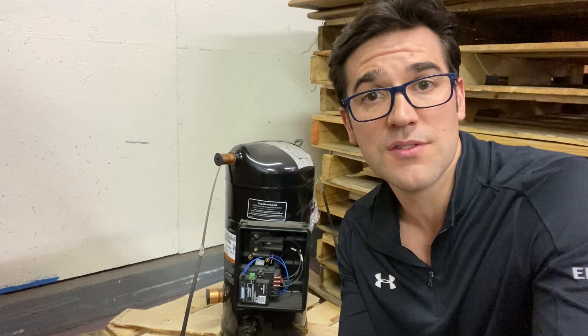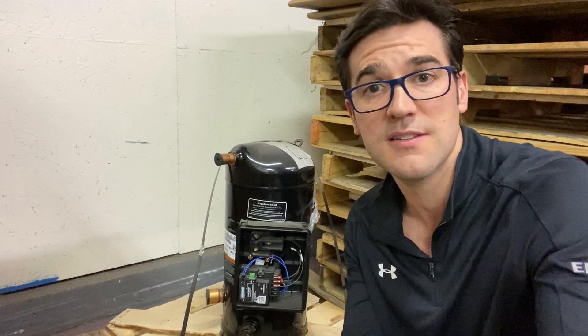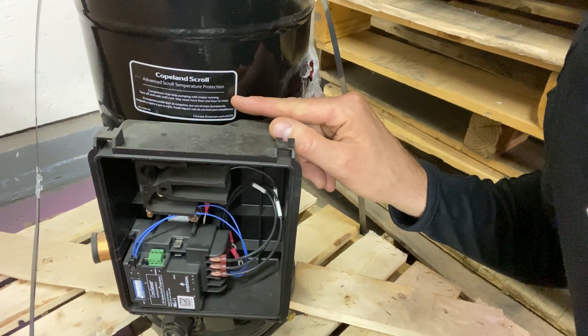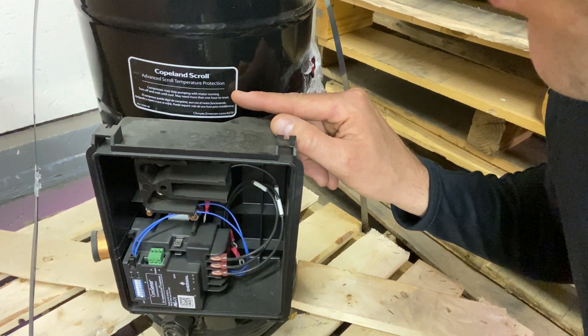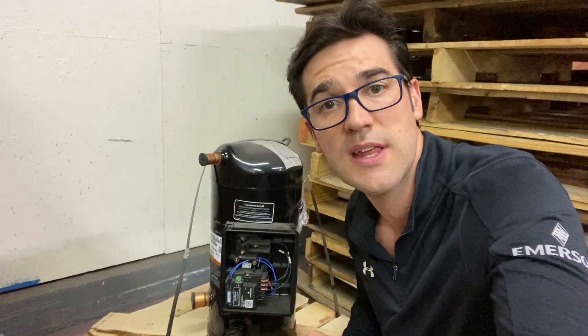It's very important to understand the different compressors you're working on, because this device is not in all scrolls — it's in some ZPs, some ZRs, some ZBs, lots of different models. The label right here says: 'Copeland Scroll Advanced Scroll Temperature Protection — compressor may stop pumping with motor running. Turn off and wait until cool. May need more than one hour to reset.' That is very important to understand.